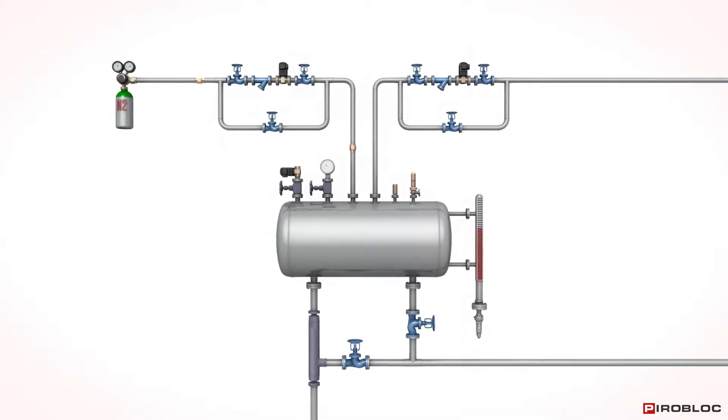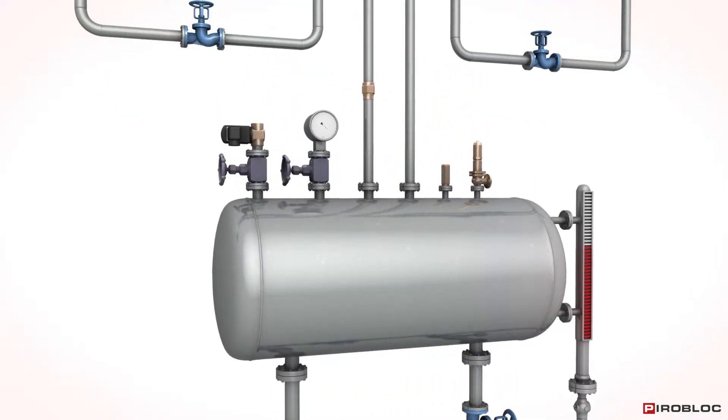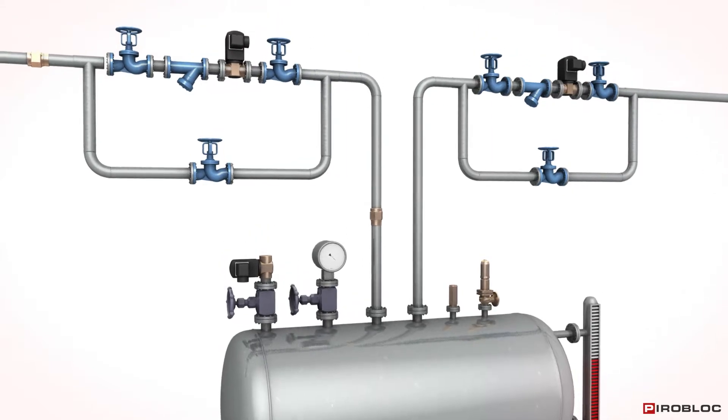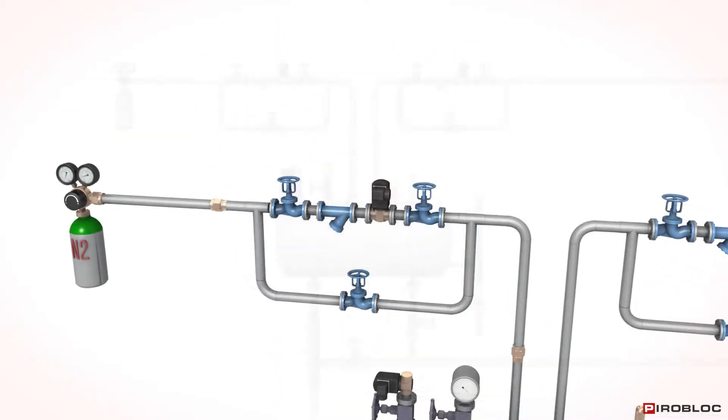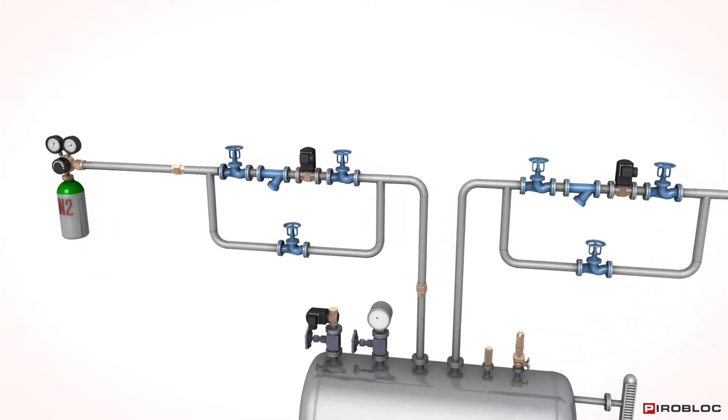In some cases, especially when the service temperature is higher than 350 degrees Celsius, 650 degrees Fahrenheit, a pressurized expansion tank is mandatory in order to avoid vaporization of thermal fluid.